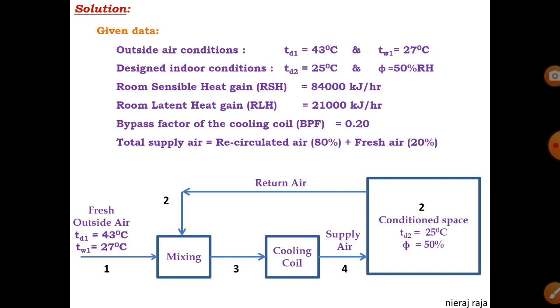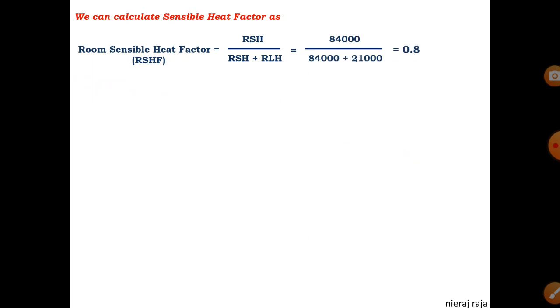Since we have sensible heat gain and latent heat gain, we can easily calculate the RSHF — Room Sensible Heat Factor — using the formula: RSHF = RSH / (RSH + RLH). The sensible heat and latent heat values are directly given in this problem. In some problems, different sources might be given and you'd add them up for sensible and latent heat, but here RSHF calculates to 0.8.